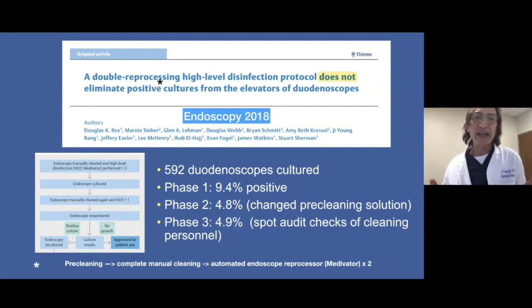So they did a phase 3 part of this study where they also did spot audit checks of the cleaning personnel, so intensifying the Hawthorne effect, and there was really no difference. So the bottom line here is, even if you do double reprocessing and you use the best pre-cleaning solution that's out there, you still cannot eliminate contamination. You still have a 5% contamination rate, and that's just not acceptable.